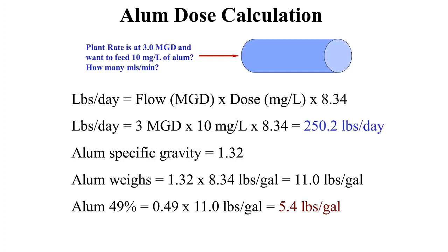The first thing you want to do is write down the formula: pounds per day equals flow in million gallons per day, times milligrams per liter, times the constant 8.34. Then we plug in our flow of 3 MGD and our dose of 10 milligrams per liter. Multiplying that out, we get a 250 pounds per day feed rate — for any treatment chemical at 3 MGD and a dose of 10 milligrams per liter.